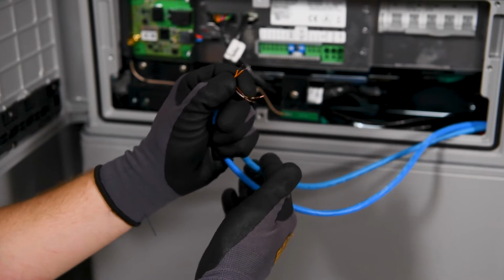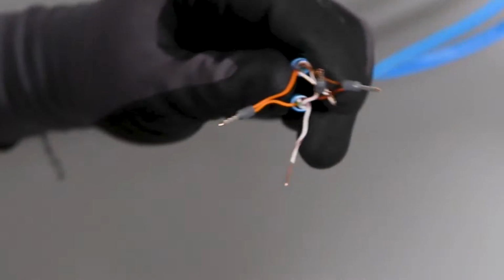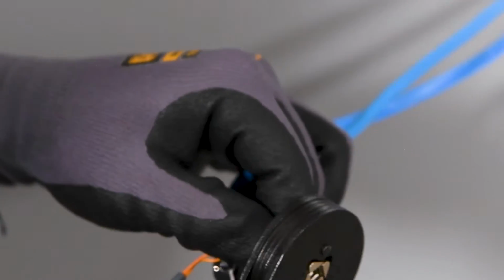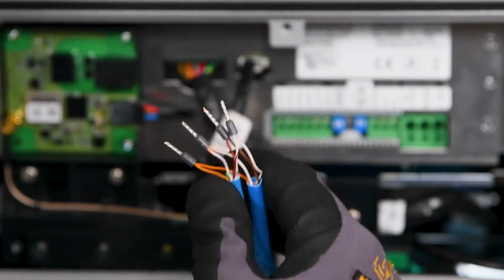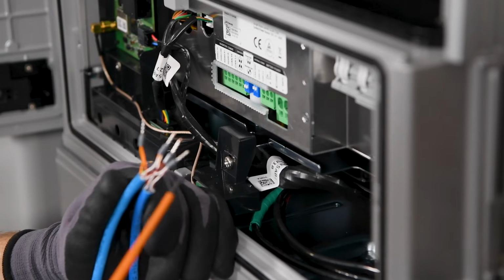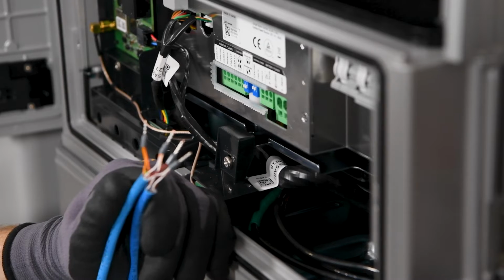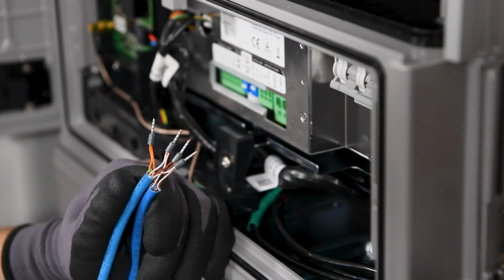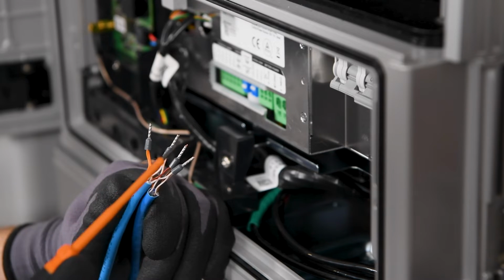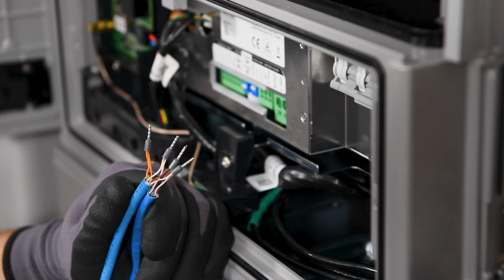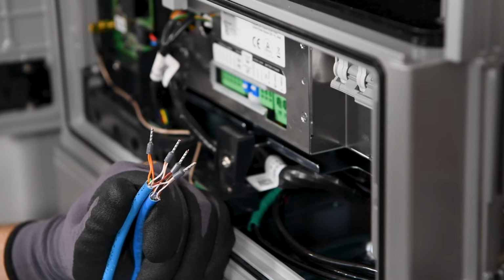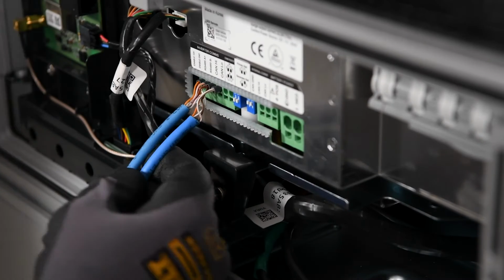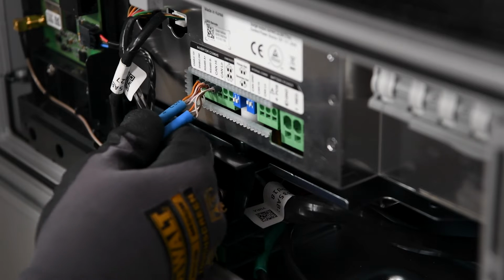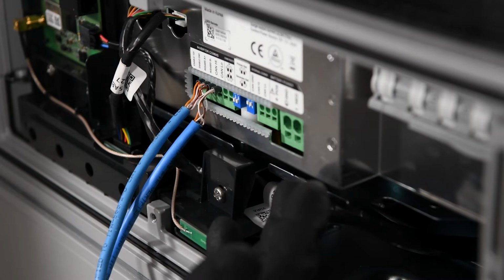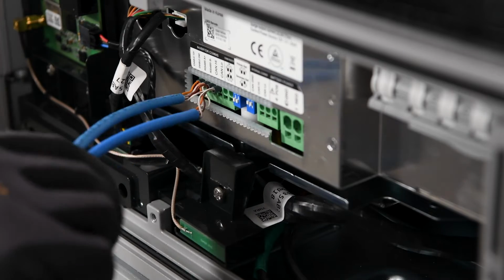When we're setting up communications within the secondary battery, I highly recommend that you use ferrule connections, especially when we're talking about double landing within this inverter comms port here. So I'm going to use ferrule connections to ensure that the continuity and the communication signal between the 2 wires is secure. We now have our 2 communication cables paralleled together with the ferrule connections. And again, we'll use orange for enable 12 volt, orange-white for enable ground or enable GND, brown for RS485A+, and brown-white for RS485B-. All of our communication cables are connected to our inverter comms ports. We'll give them a slight tug just to ensure that there's good continuity there and that the jaws or the teeth in the communication port are holding onto the cables tightly.